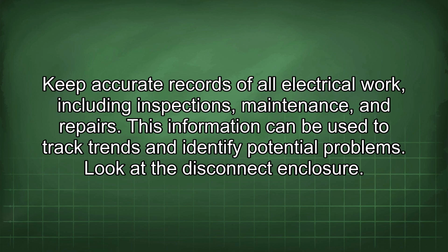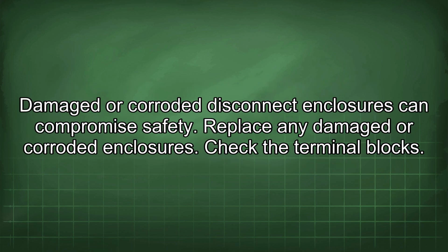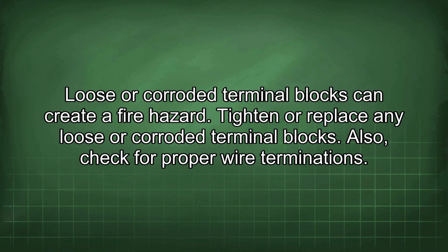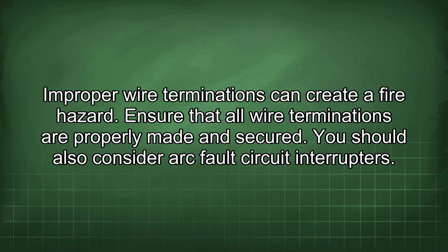Look at the disconnect enclosure. Damaged or corroded disconnect enclosures can compromise safety. Replace any damaged or corroded enclosures. Check the terminal blocks. Loose or corroded terminal blocks can create a fire hazard. Tighten or replace any loose or corroded terminal blocks. Also, check for proper wire terminations. Improper wire terminations can create a fire hazard. Ensure that all wire terminations are properly made and secured.